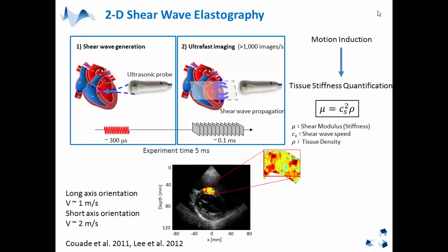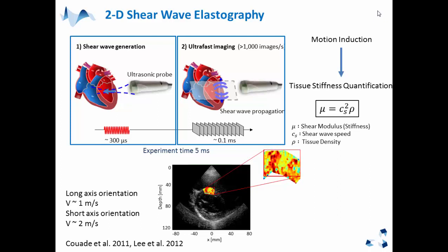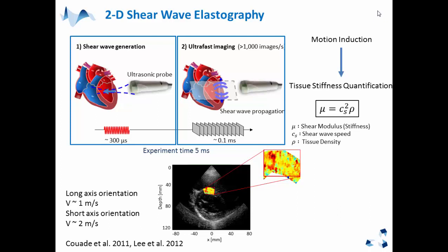However, in the cardiac field, for example, the heart is anisotropic tissue. If we take a short-axis parasternal view, we will find shear wave velocities around 2 meters per second. And then, if we rotate the probe 90 degrees in the same position to a long-axis parasternal orientation, we will obtain shear wave velocities around 1 meter per second. This means that shear wave elastography is sensitive to tissue anisotropy, and probe orientation is very important for a good shear wave velocity estimation.